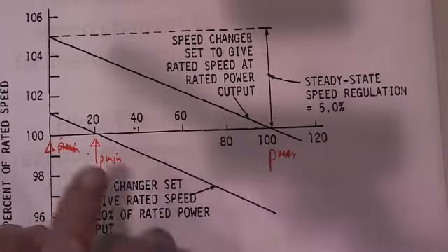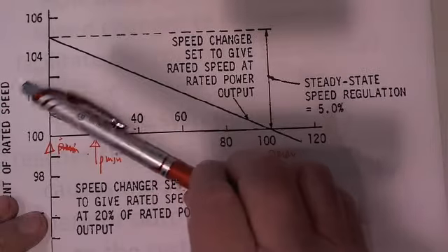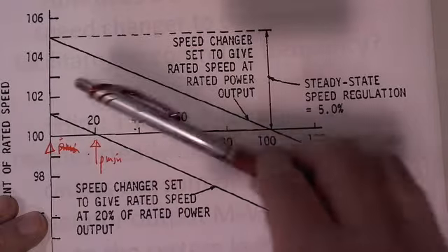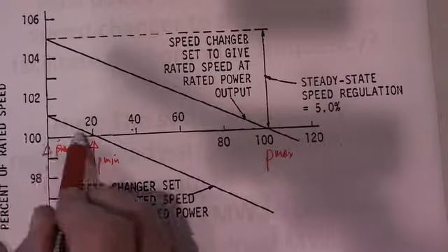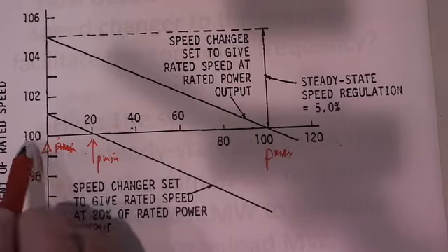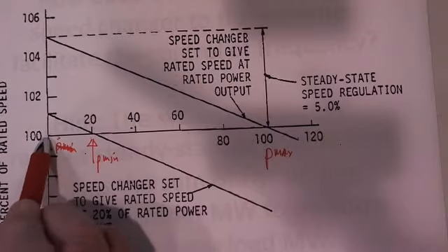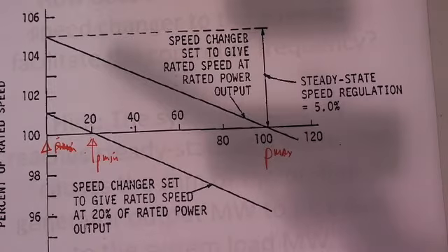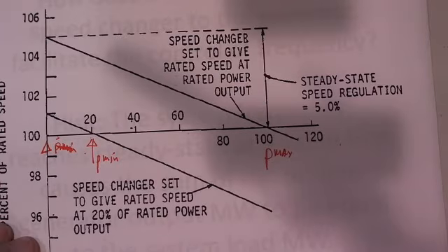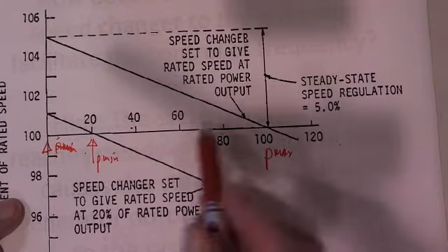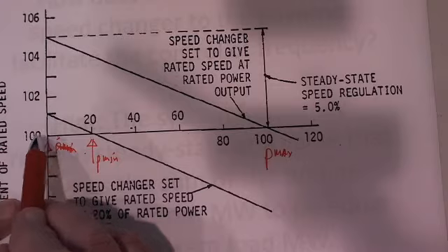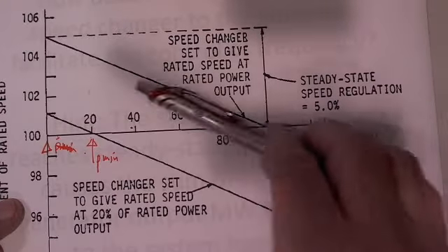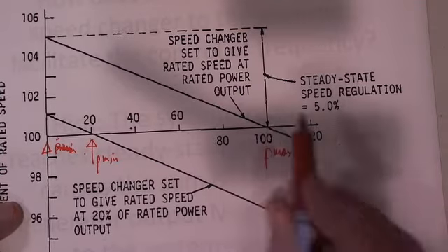Okay, and so I can move this characteristic with my pen. I can move it back and forth. And here I would keep the standard frequency, or this is percent of rated speed, 100%. Well, let's say for 60 hertz, depending if it's a two-pole generator. Then you can go back and say, well, how many RPM does that come out to be? If it's a 24-pole generator like a hydro system, what's that one come out to? Anyway, this is 60 hertz here, and if I move this over, I get more power out at the same frequency. Okay, so that's called the speed changer.